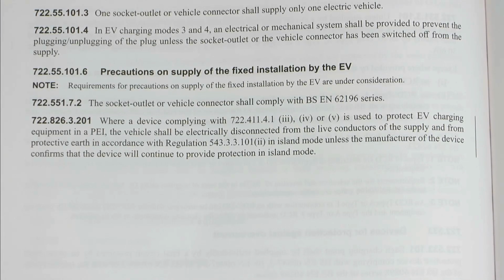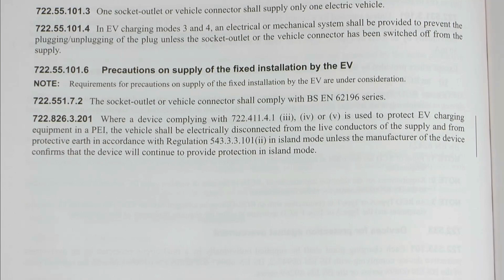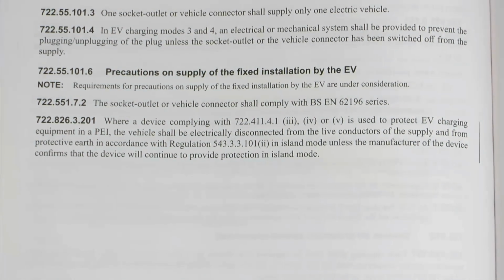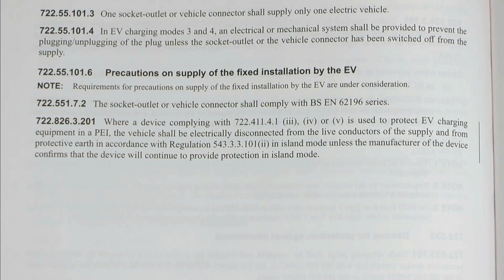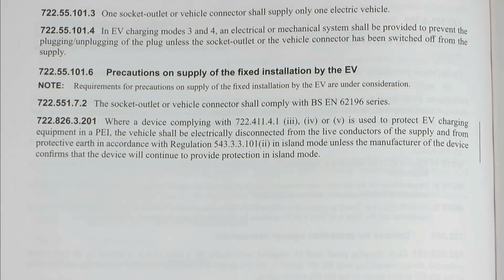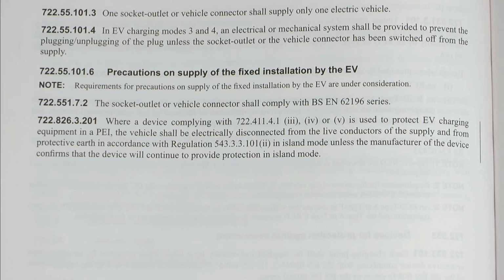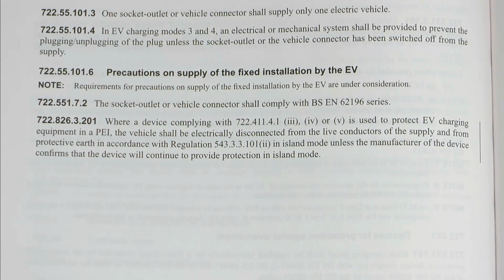And the last thing in that particular one, 722, is at the end here. This is a new one. It's 826.3.201, and this fits in with Part 8, which we'll look at in the next video. Now this is where a device complying with 722.411.4.1, indent 3, 4 or 5 is used to protect EV charging equipment in a prosumer's electrical installation. The vehicle shall be electrically disconnected from the live conductors of the supply and from the protective earth in accordance with regulation 543.3.3.101.2 in island mode, unless the manufacturer of the device confirms that the device will continue to provide protection in island mode. And so we'll look at what island mode is in the next video.